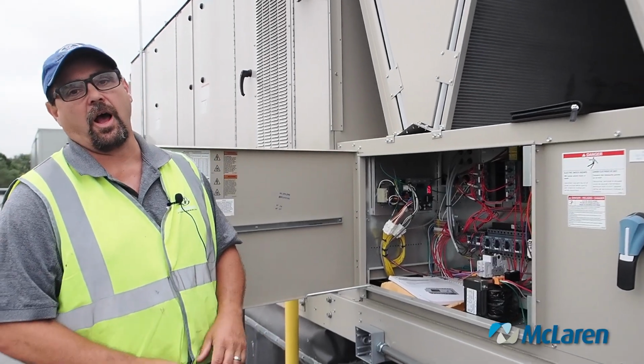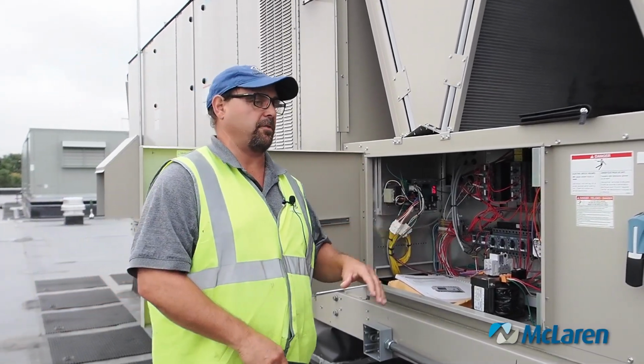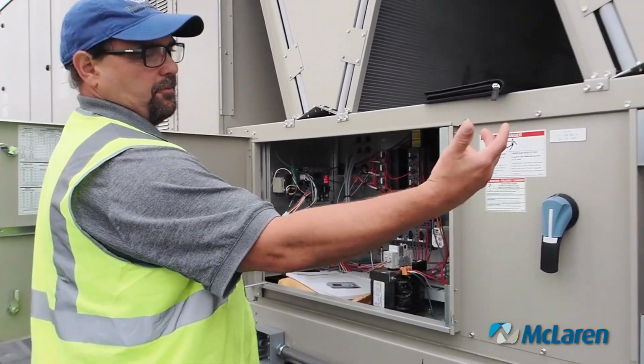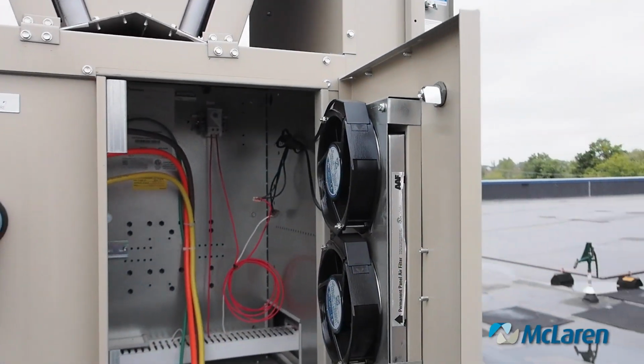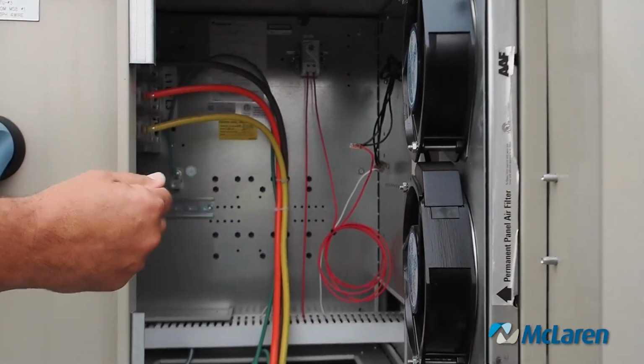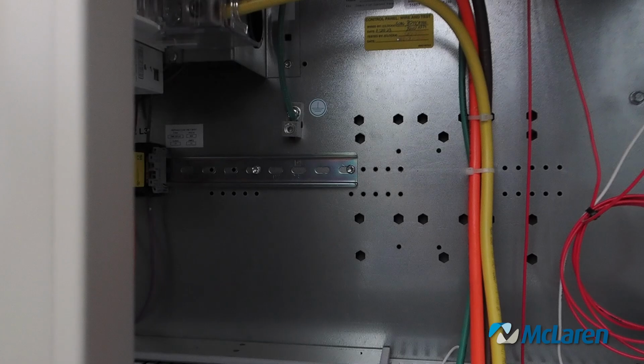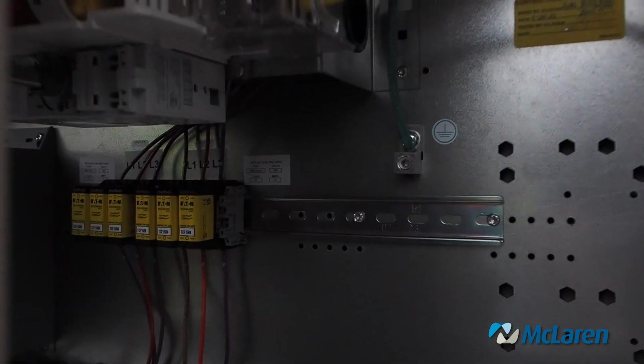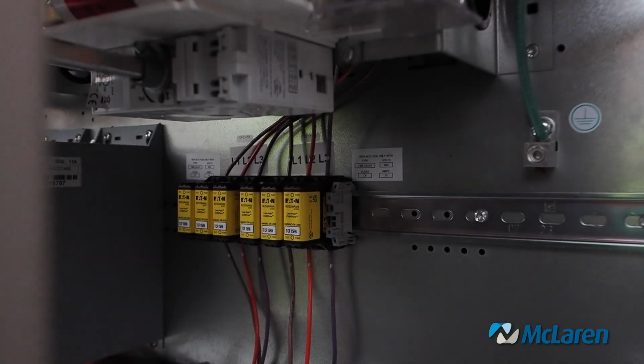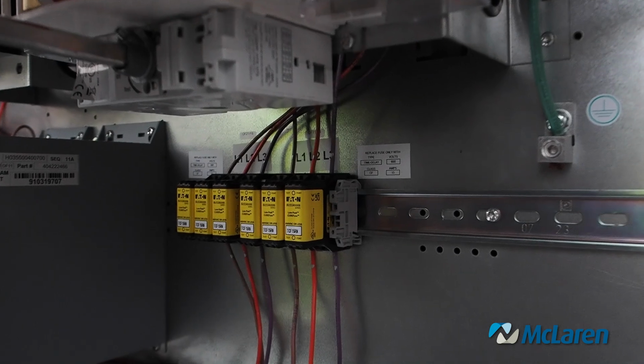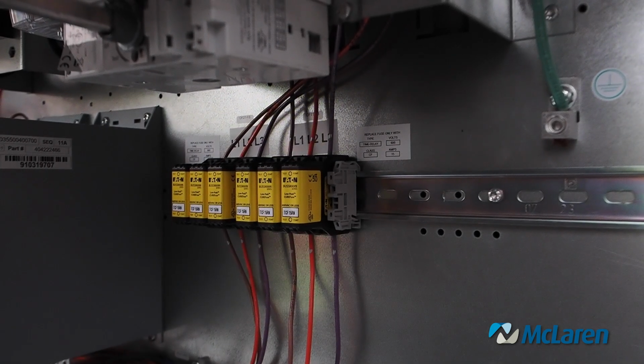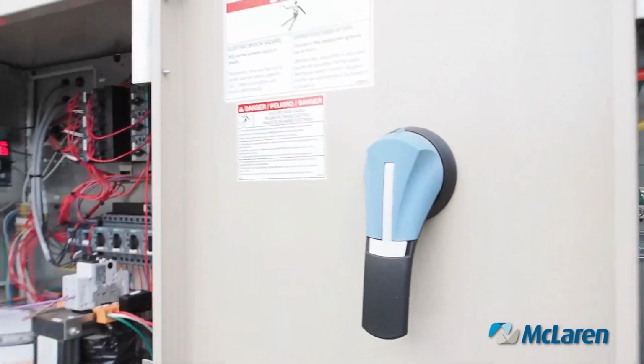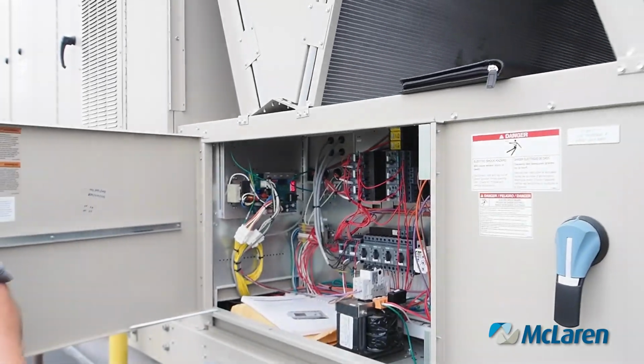Inside of here is your higher voltage control compartments. As you can see, you have your incoming voltage powering up the unit coming through that panel. If you could get a side view of it, there are fuses back in there to the left that say L1, 2, and 3. Those fuses monitor the voltage feeding the condenser fan drives. If there's a problem on one of those drives, those fuses could blow.